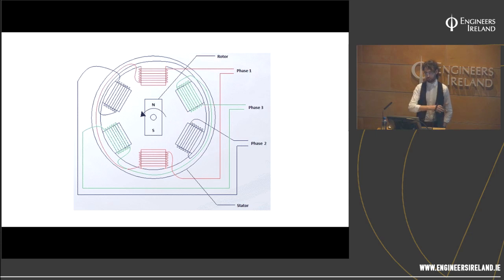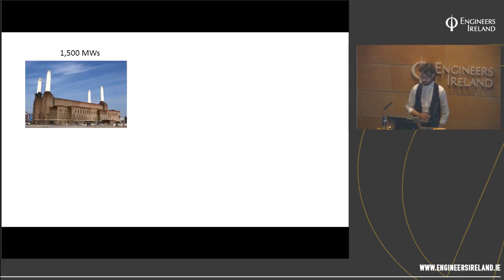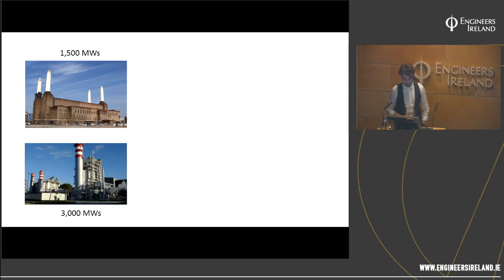To give you a feel for it, power systems are diverse, and so are the inertial sources. Here we have a coal plant. Typically, they have a stored energy of 1,500 megawatt seconds. I'll put that number in context in a minute. I just want to compare at the moment. This is a combined cycle gas turbine, probably the most popular technology on the Irish system at the moment. You're looking at around 3,000 megawatt seconds typically.